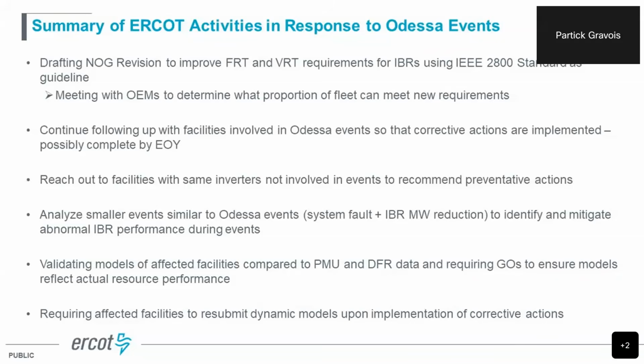We're going to continue to follow up with the facilities involved in both events to make sure these corrective actions are implemented. It's looking like all of this will be implemented by the end of the year. A lot of it's been done already, but we're staying in close communication with these facilities to make sure these things are happening. We're also going to reach out to all the facilities with the same inverters involved in these events to recommend these same actions: volt phase jump, extending the threshold or disabling it, extending voltage and frequency ride-through, things of this nature. So we're going to do a lot of outreach next year to the rest of these facilities not involved in these events.